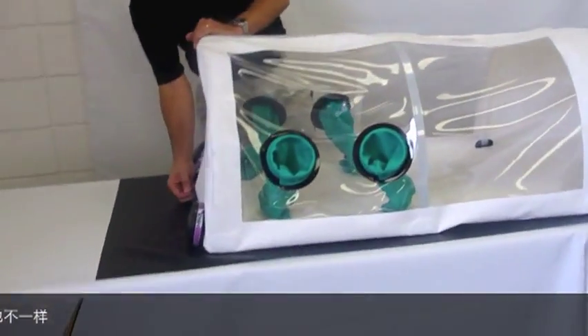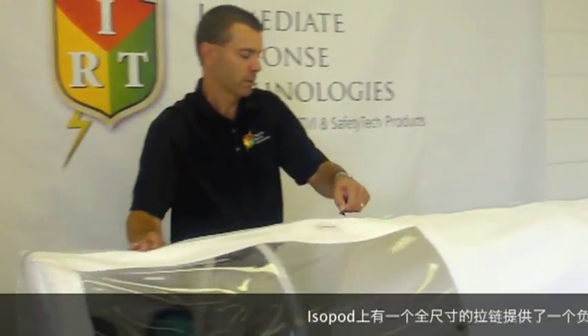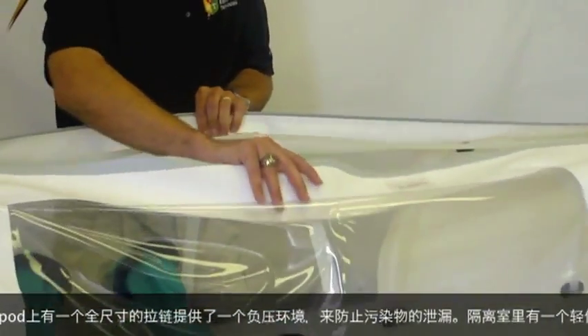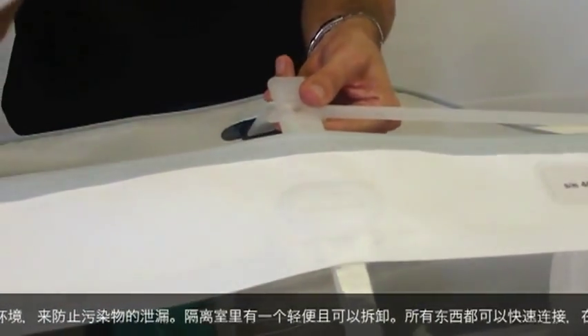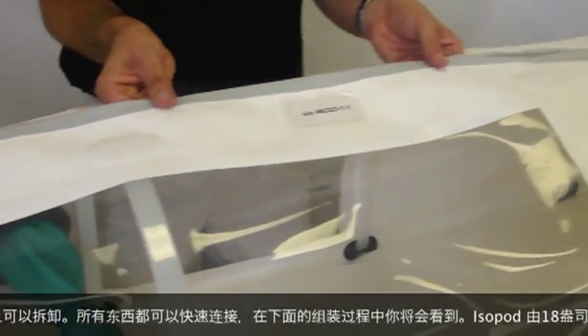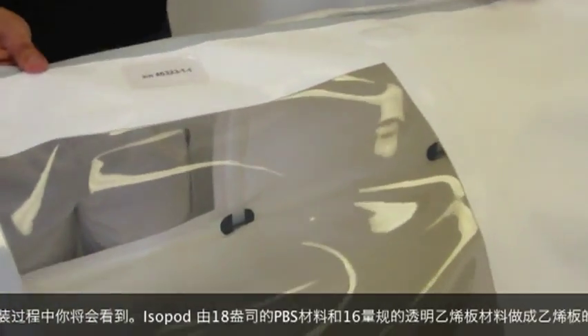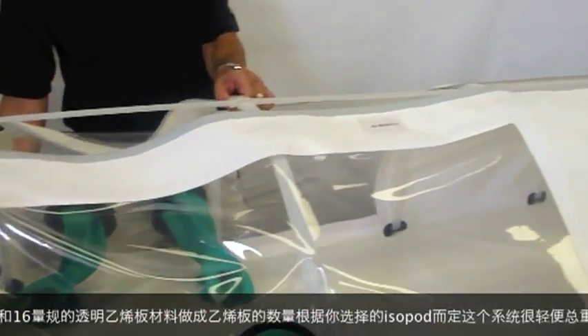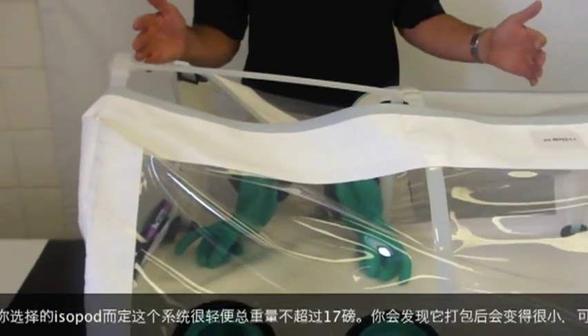With regards to the isopod, you have a full-length zipper which helps prevent contaminants from escaping during a negative pressure application. Inside the isolation chamber, there is a ribbing that's lightweight and easily removable. Everything is QuickConnect, which you'll see more during the setup. The construction of the isopod uses 18-ounce PVC and 16-gauge clear vinyl panels. The number of panels depends on the options that you select. The system is very lightweight, weighing with all components just under 17 pounds, and packs into a very small, roughly 3x2 duffel bag.